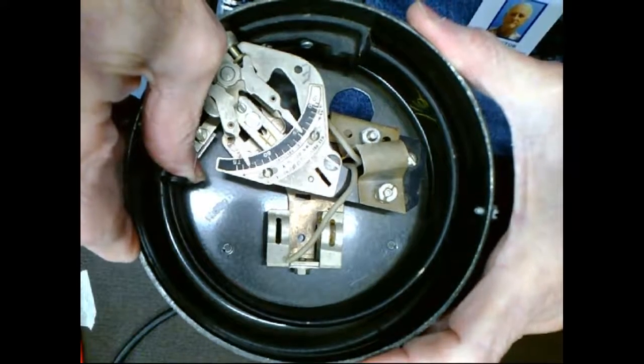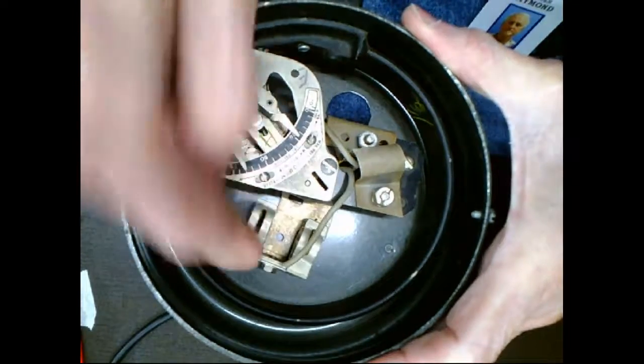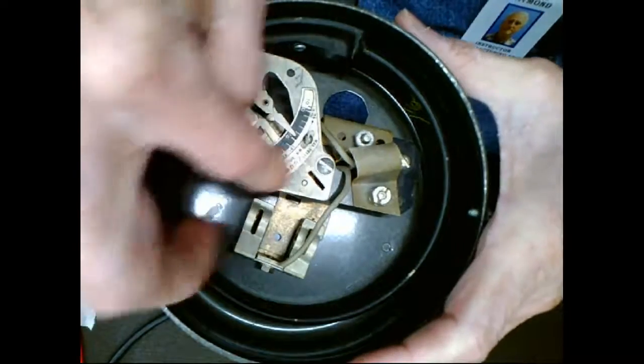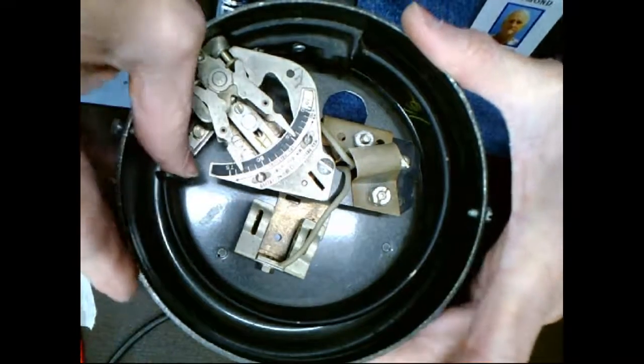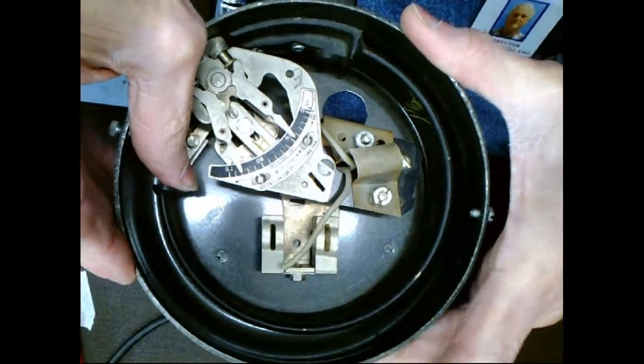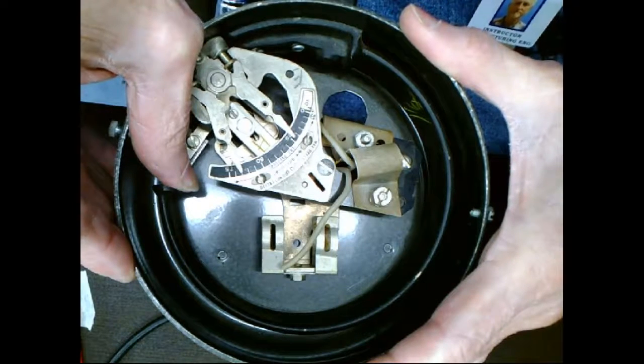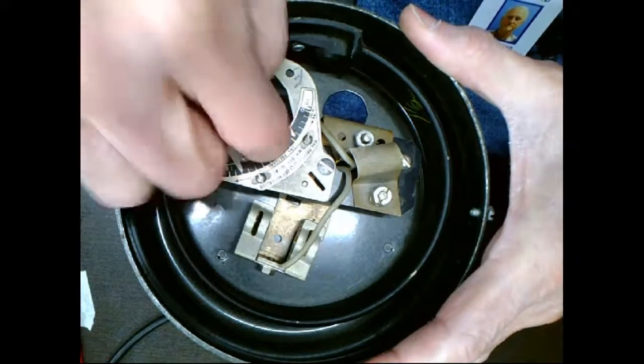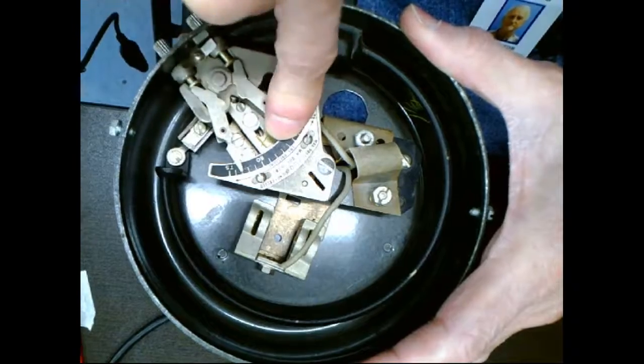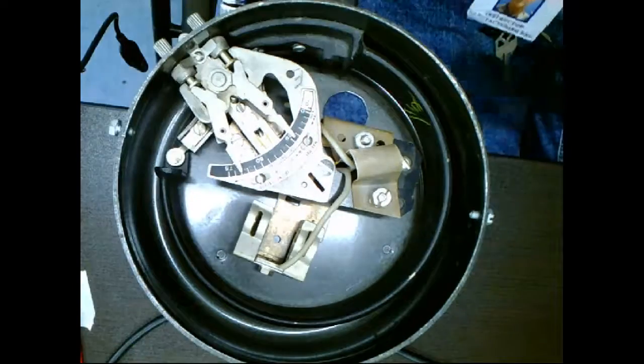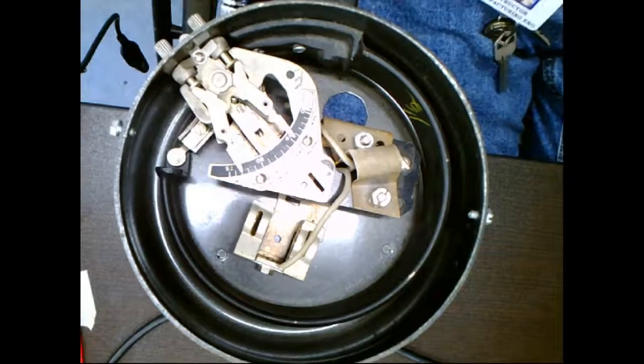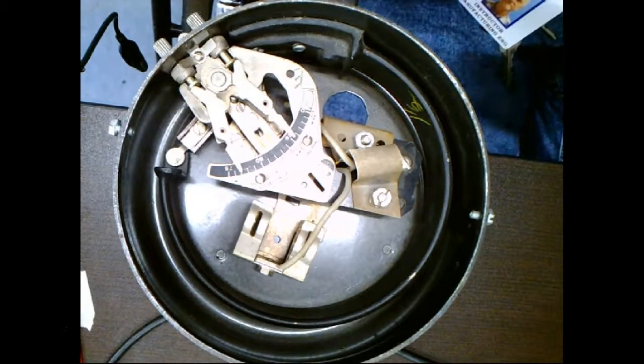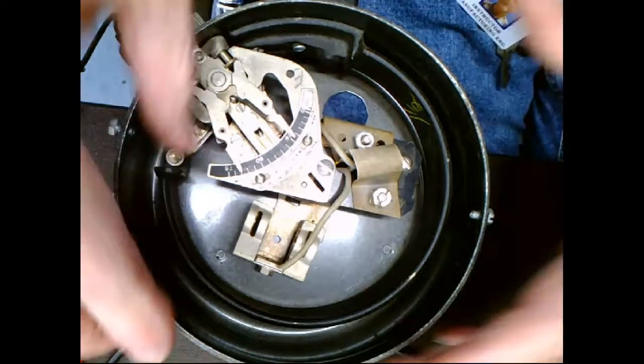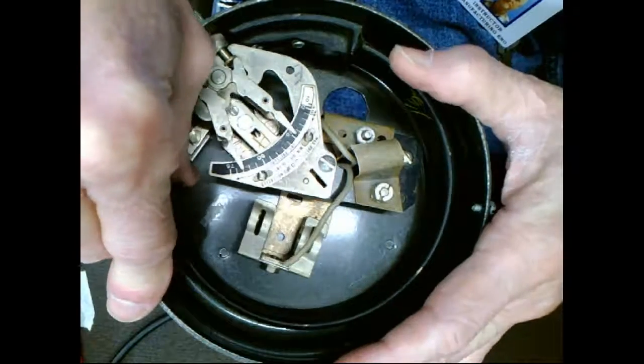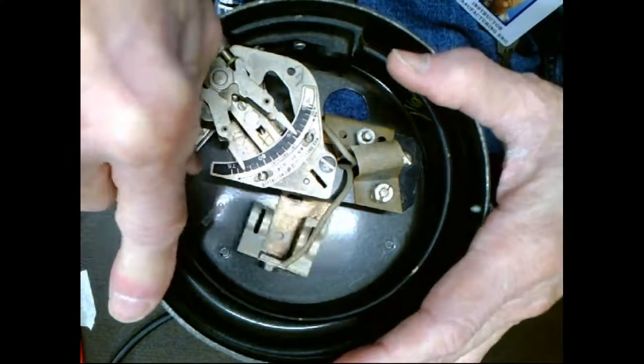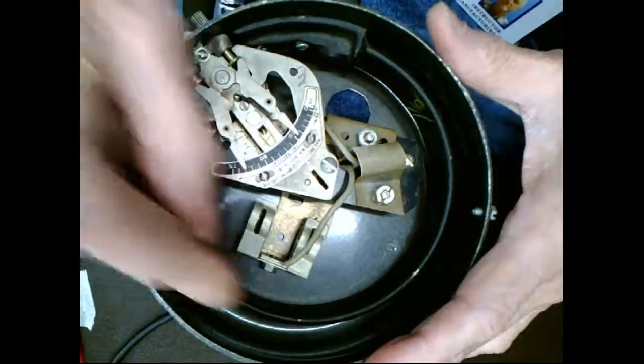All of a sudden - this used to be a mercury switch, and I can set that so when this thing comes up and hits a certain point, it just switches. So I could come up here and change this angle, and then change it for when the pressure was too big or too low. That makes sense? So this is a Bourdon tube. These have been around, and they're still used a lot. Very simple concept.